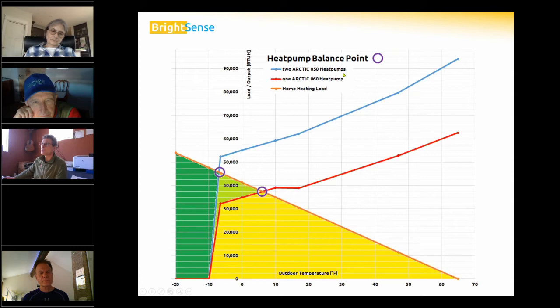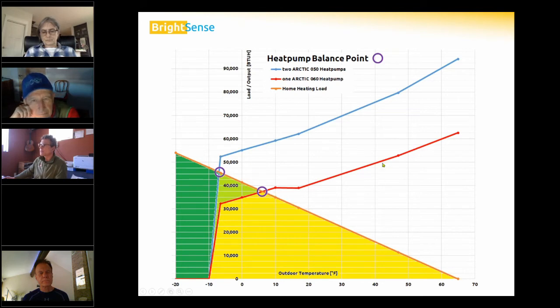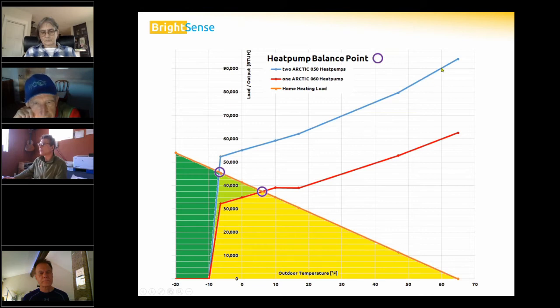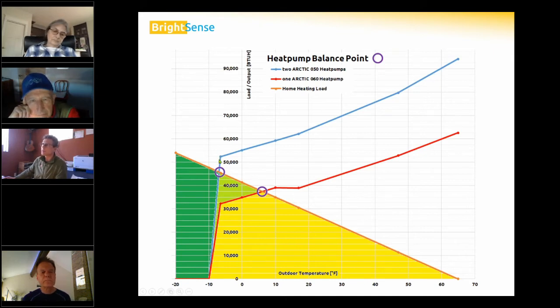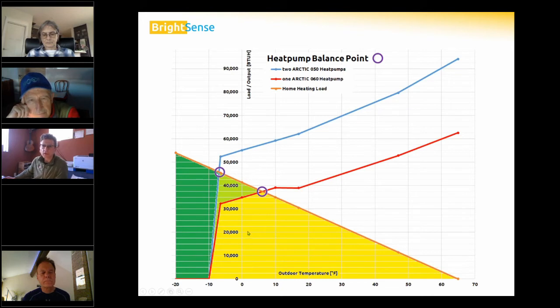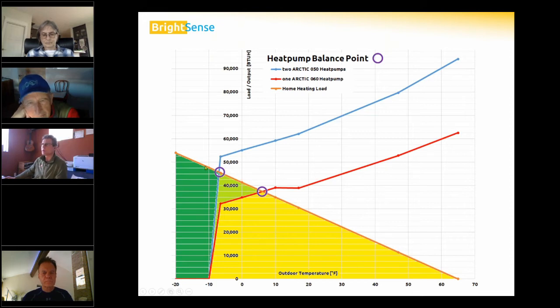This is the 50-unit model delivering about 60,000 BTUs. As you can see, those outputs go down the colder it is. We need to match that with the heating load of our building. When doing a Manual J heating load simulation, where those two curves intersect is called the balance point.